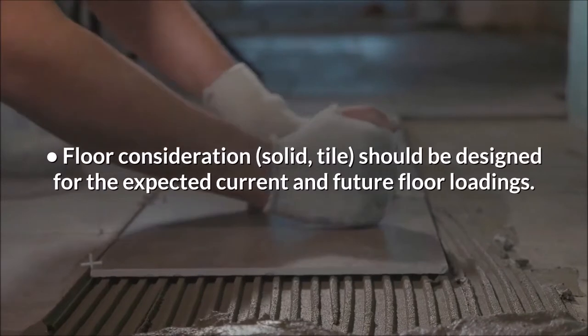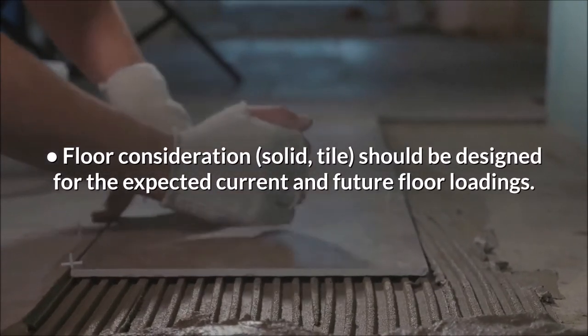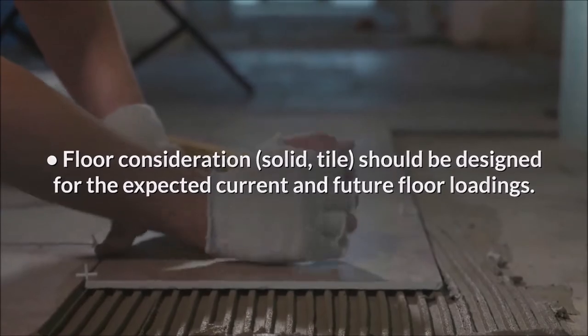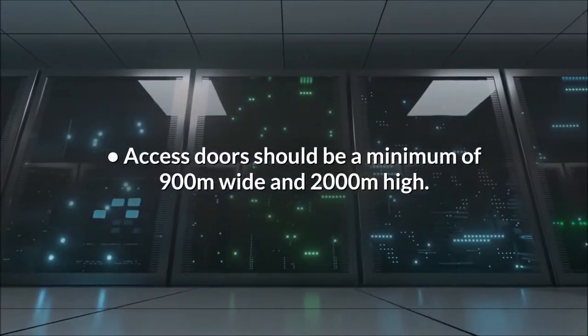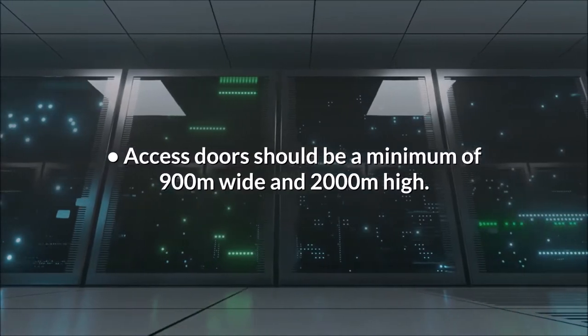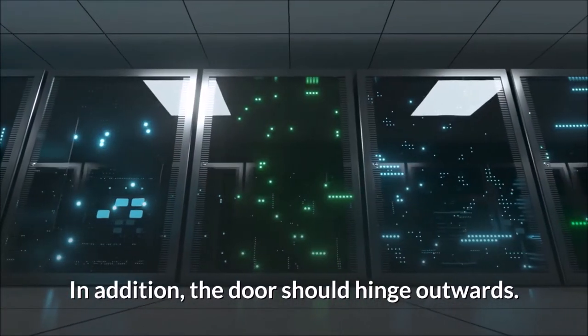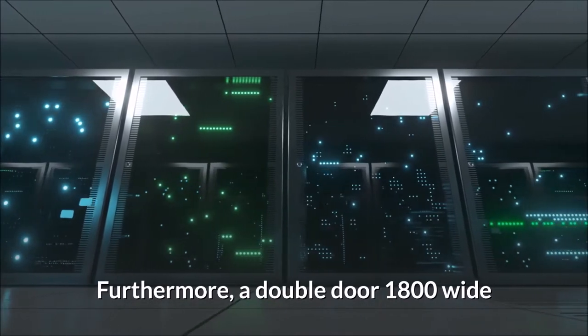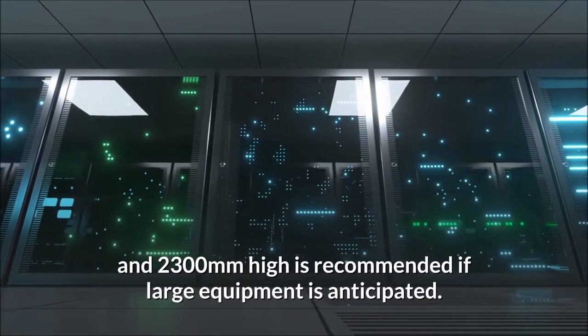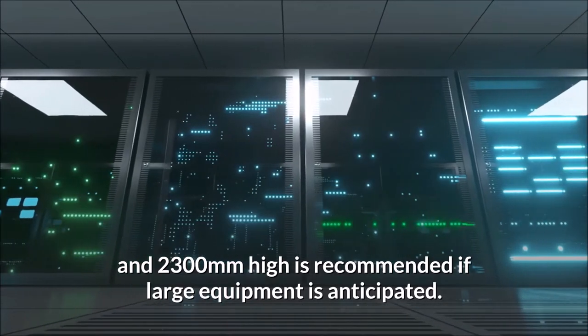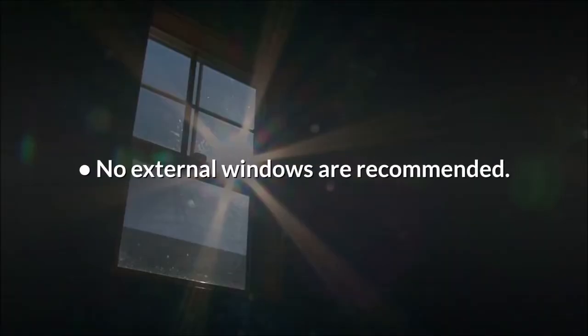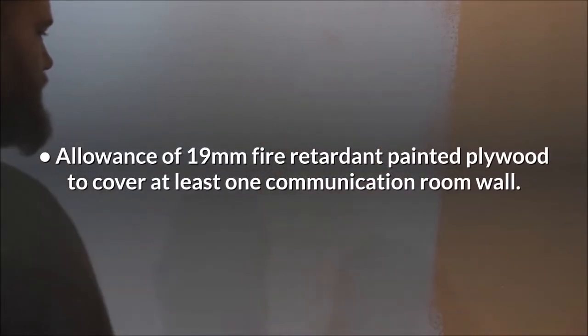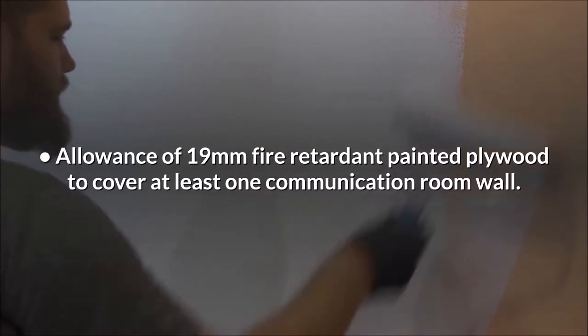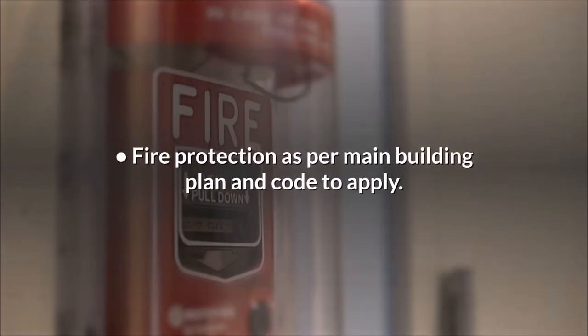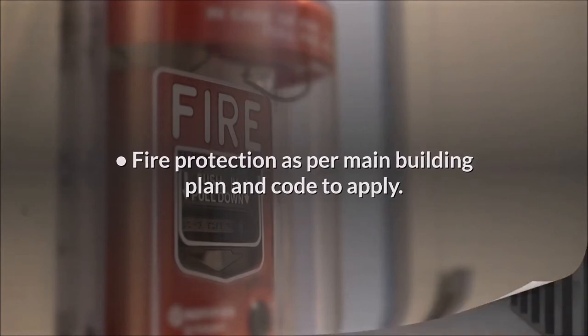Floor consideration: solid, tile, should be designed for the expected current and future floor loadings. Access doors should be a minimum of 900 mm wide and 2,000 mm high. In addition, the door should hinge outwards. Furthermore, a double door 1800 wide and 2300 mm high is recommended if large equipment is anticipated. No external windows are recommended. Allowance of 19 mm fire retardant painted plywood to cover at least one communication room wall. Fire protection as per main building plan and code to apply.